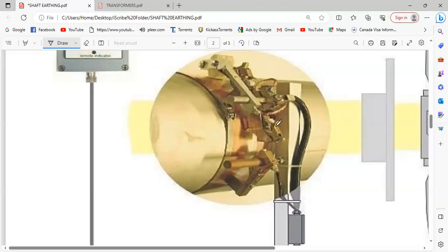Okay, so that's why this is holding it down, but it should hold it down with a certain amount of pressure, not too much. They normally have 3 settings: light, medium, and heavy pressure. If you put it on the third setting, it's going to press down fully onto these brushes, and your silver graphite brushes can get worn out very, very rapidly. If you put it too light, then this sometimes may or may not make contact, in which case you're not having adequate protection. So generally it is kept in the middle, so that sufficient pressure is exerted on these brushes, 1, 2, and 3, so that you get a proper reading.